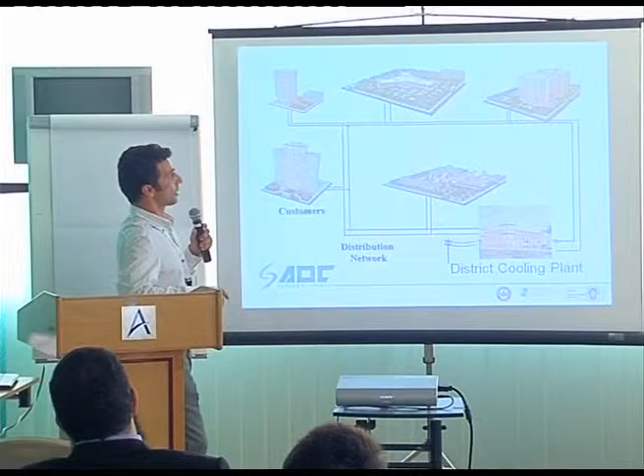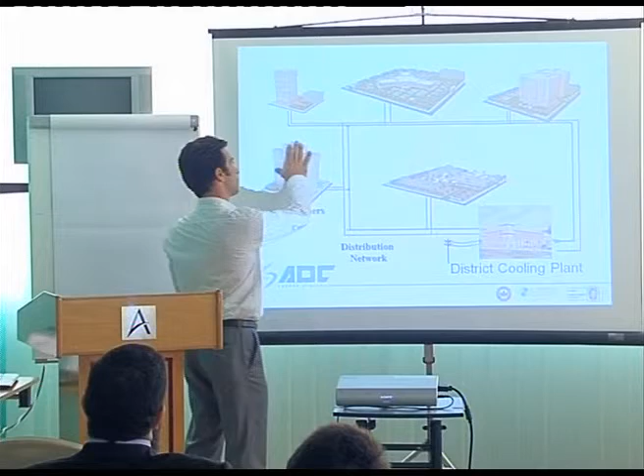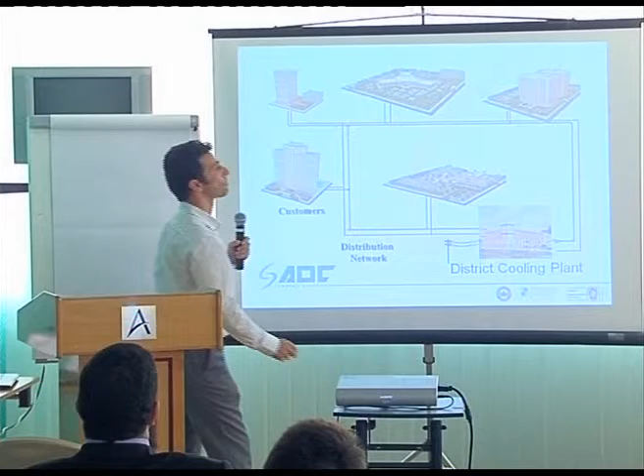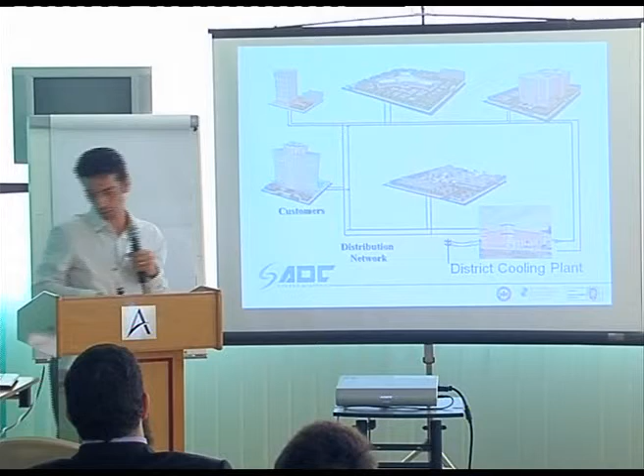These customers are connected through what we call an ETS station—an energy transfer station—normally with plate heat exchangers that decouple the buildings from the network. The network can work independently of the building's height, its hydraulics, or whether the building is finished or not. For example, if three buildings are running and a fourth is not, you need to cap it off somewhere, since cooling has to be given to certain buildings before others, so the system can continue to grow.